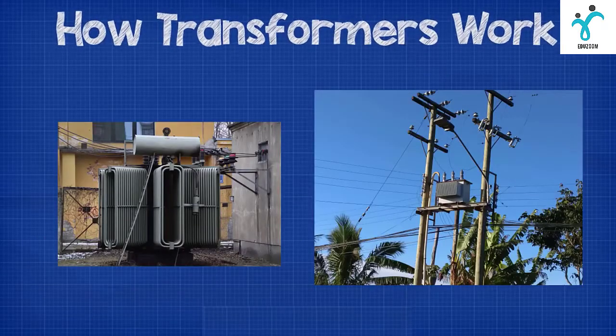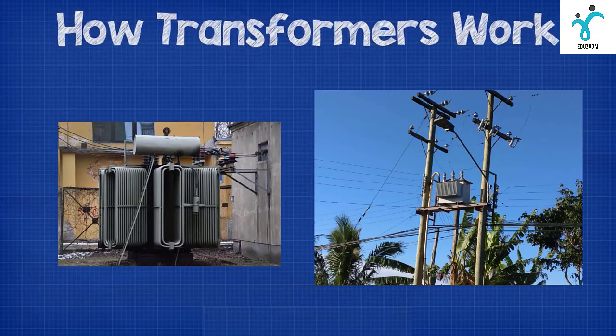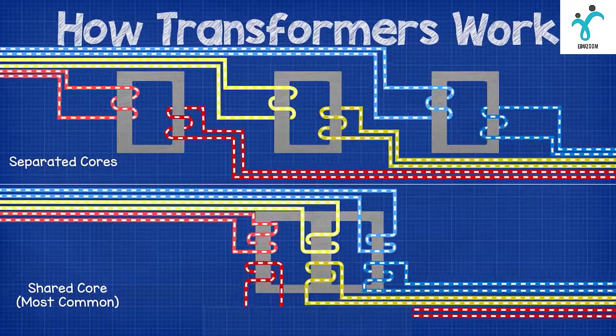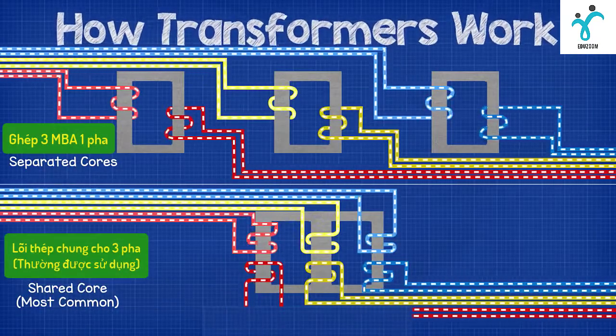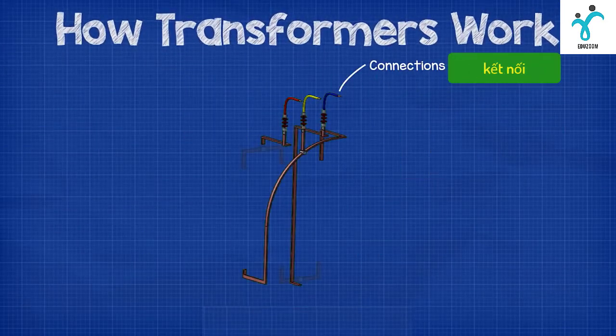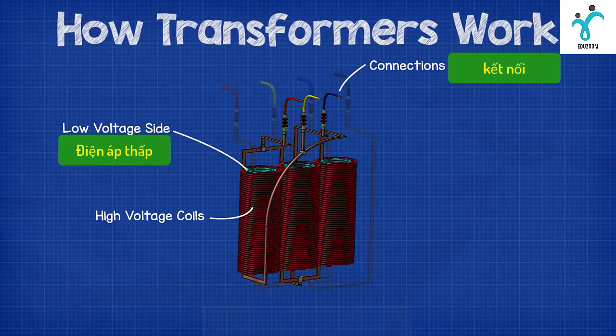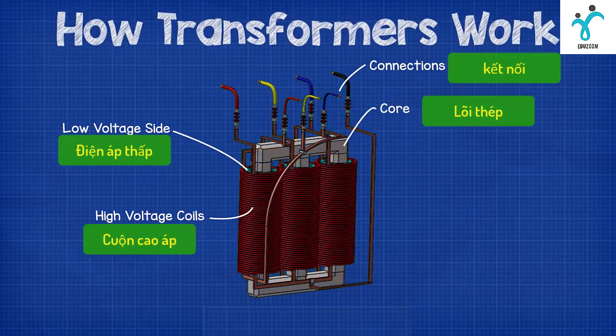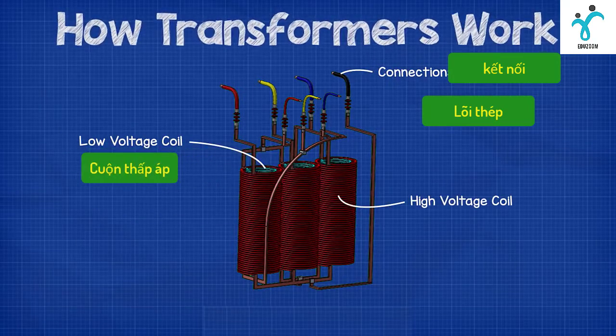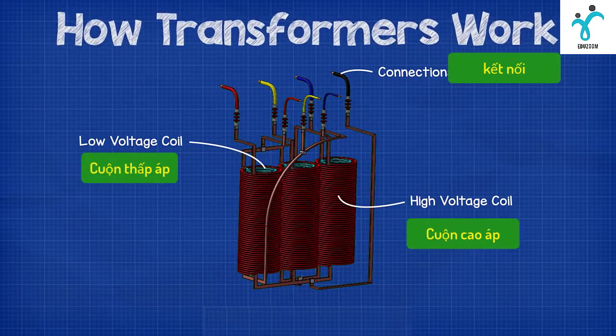The transformers for commercial buildings and power stations are usually in a three-phase configuration. You'll see these placed around your cities and towns and they'll look something like this. These three-phase transformers can be made from either three separate transformers that are wired together, or they can be built into one large unit with a shared iron core. In this setup the coils will typically sit concentrically within one another, with the higher voltage coil on the outside and the lower voltage coil sitting on the inside. These coils are insulated from one another so that only the magnetic field will pass between them.